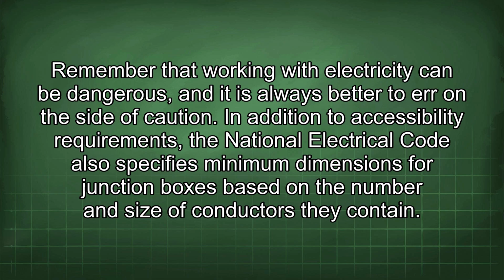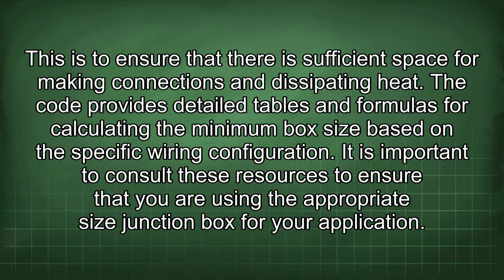In addition to accessibility requirements, the National Electrical Code also specifies minimum dimensions for junction boxes based on the number and size of conductors they contain. This is to ensure that there is sufficient space for making connections and dissipating heat. The code provides detailed tables and formulas for calculating the minimum box size based on the specific wiring configuration. It is important to consult these resources to ensure that you are using the appropriate size junction box for your application.